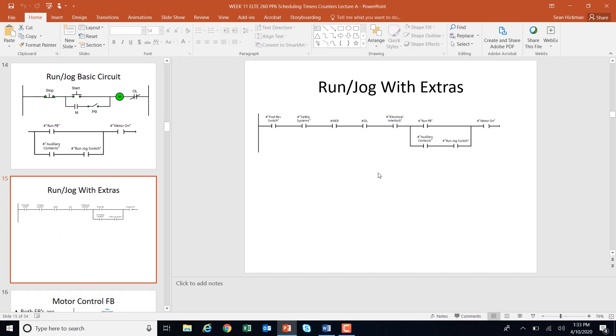Here's run/jog with extras. If I need a forward switch, overload safety systems, an e-stop, MCR, and an electrical interlock — wired normally closed so I can't have one motor on when the other is on — plus a run/jog switch, when I hit run I either get the motor on or with the jog switch I can get memory. Auxiliary contacts hold the memory. That's a fancy run/jog with extras.